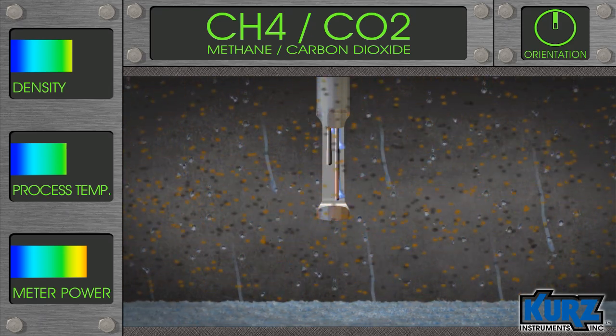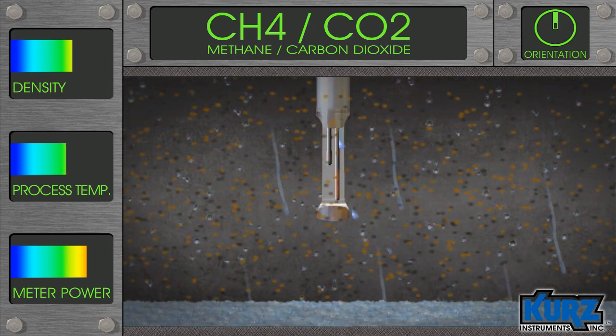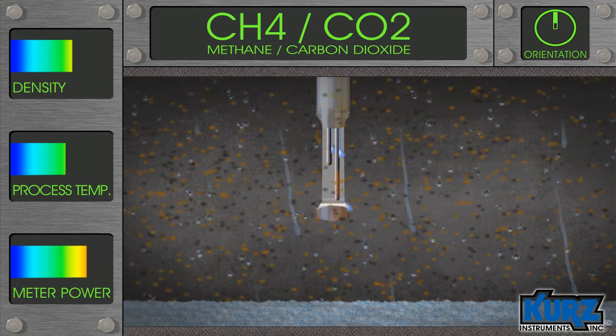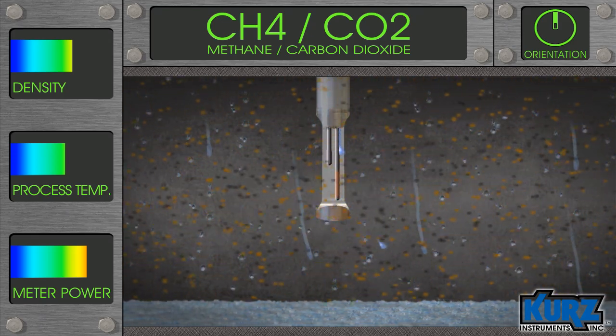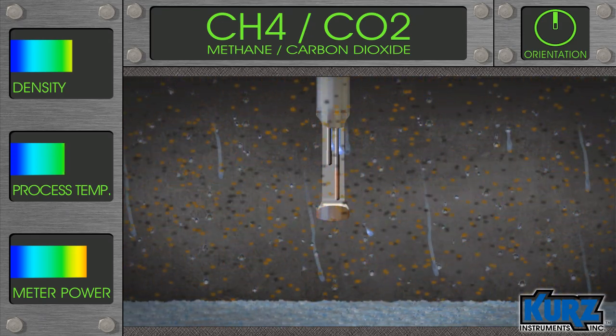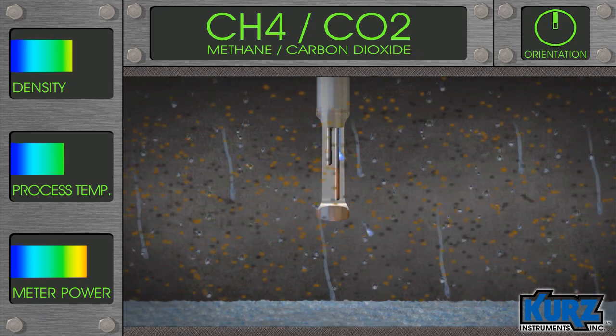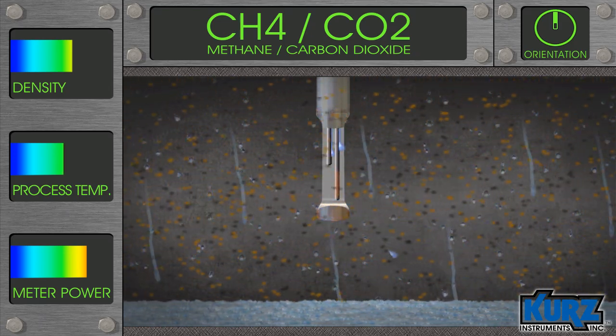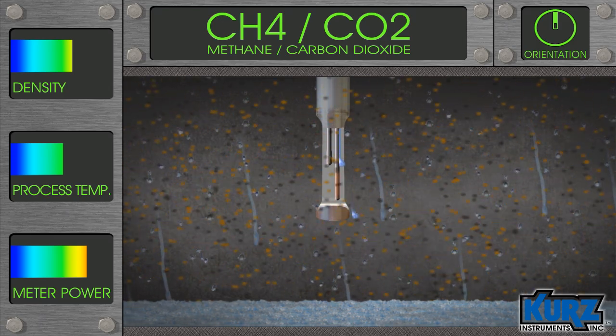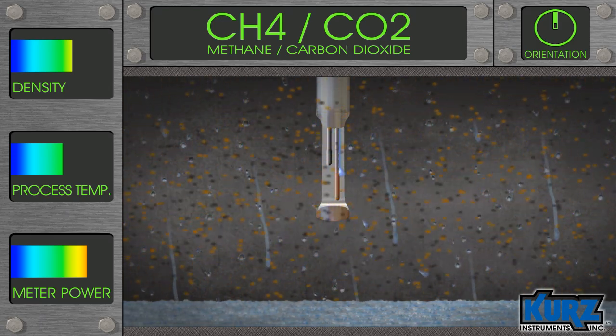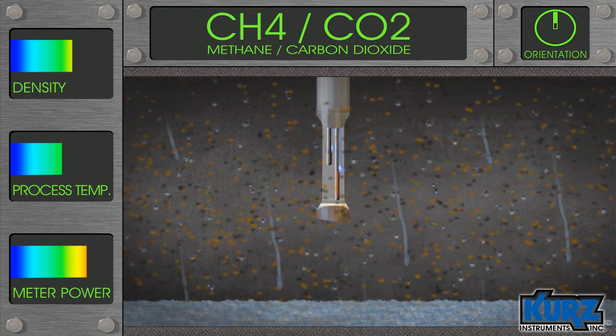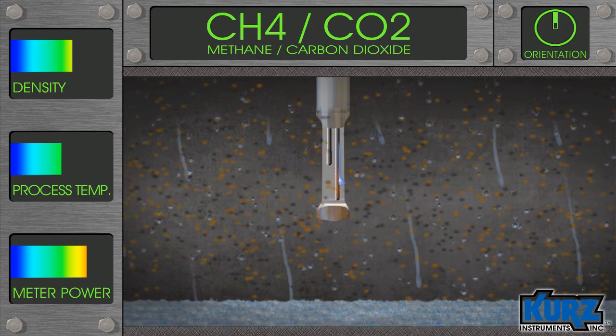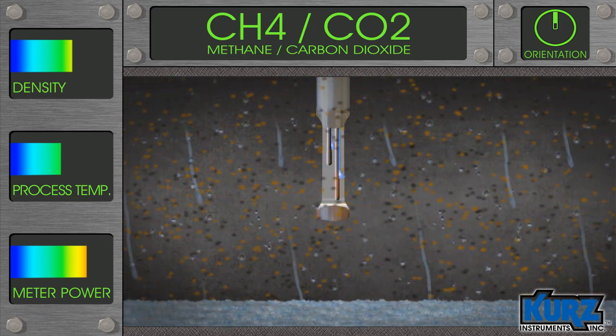Long cooling periods result in large water droplets forming in the biogas flow, causing water to collect on and drip down the pipe walls. Sensors that have a low overheat are unable to vaporize all the water in larger drops. The excess water spreads across the heated sensor and causes spikes in poor readings. Depending on the overheat, it can take up to 30 minutes for a thermal meter to recover from a large water impact.